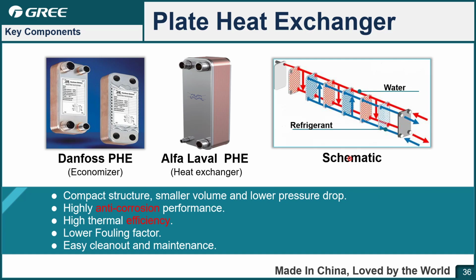Next one, the plate heat exchanger. For the VERSATI 3, there are two plate heat exchangers. One is the economizer. Another one is the heat exchanger in the hydro box. So the unit can get the hot water by the heat exchange between the refrigerant and the water. And also, due to the material, the heat exchanger is anti-corrosive. The thermal efficiency of the plate heat exchanger is very high compared with the tube and other types of heat exchanger. Also, the size is small, so that we can put this component in the outer unit or in the hydro box to keep them together.